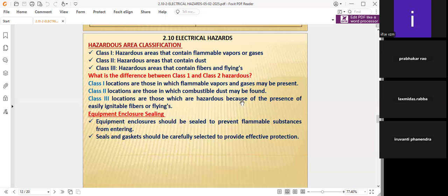Class 3 locations are those which are hazardous because of the presence of easily ignitable fibers and flyings. Where textile industries are there, where fine particles are there, we have to watch for that. In the paper industries also, chipper dust is there, where dust blowers help with the accumulated dust and the dust extraction system must be properly run. Otherwise, the dust will accumulate on the motor, the electrical equipment or the electrical circuits. Somewhere else I have seen some panel doors kept open simply, not properly closed. Therefore, atmospheric dust, process dust or hazardous dust will accumulate on the circuit over a prolonged time. Therefore, the circuit will be ignited, and thereby fire will occur.